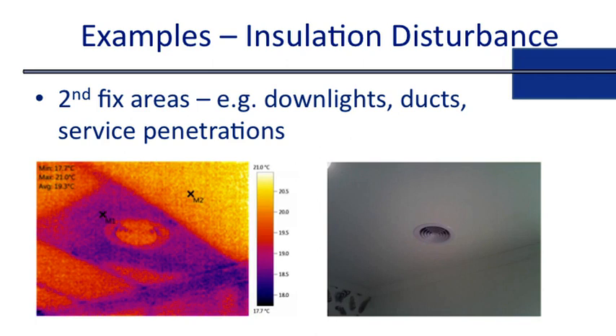Second-fix areas are generally a pretty big issue within our Australian construction industry at the moment. Here we've got a return duct — same concept, batts are moved. More often than not, they're actually up there but they've just been moved and not put back. Here we've got a correct versus incorrect installation — this is an IC-rated downlight, meaning you can lay insulation straight over the top. One image shows a batt missing completely, which is quite a large area. Without thermal imaging, most homeowners wouldn't actually be aware of what's happening in their roof.